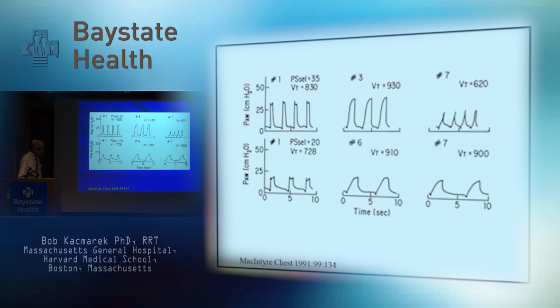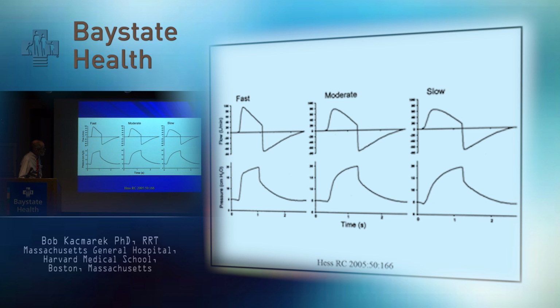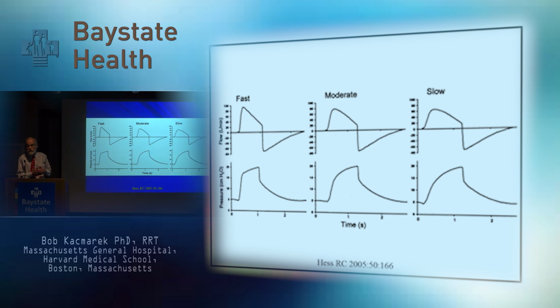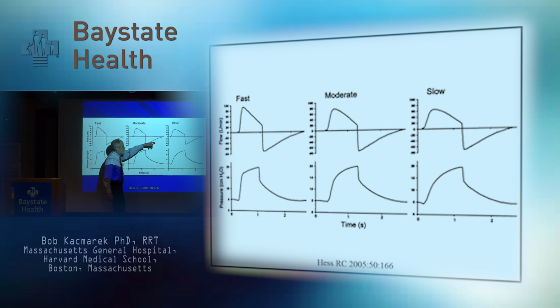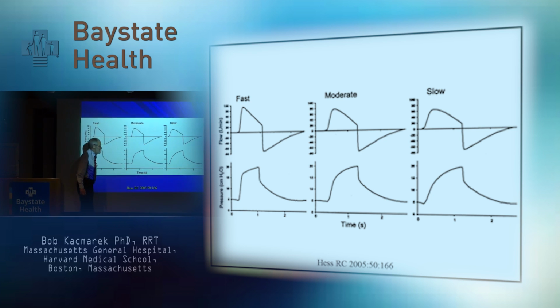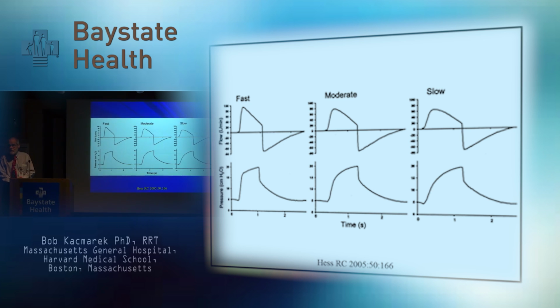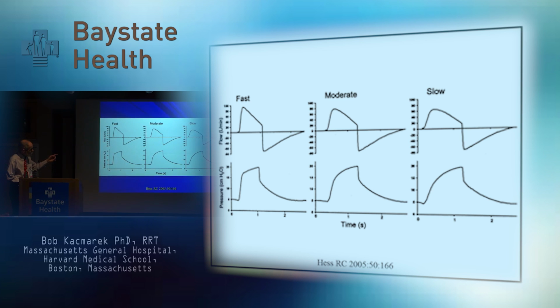And in every mechanical ventilator that I'm aware of today that delivers pressure modes of ventilation, in all pressure-targeted modes of ventilation, rise time is operational. So it allows you to vary how quickly flow goes from 0 to maximum. And in doing that, there is some change in the peak flow that's actually developed. And what we should be doing is making that adjustment in order to ensure that the delivery of pressure-targeted ventilation, again, doesn't result in flow asynchrony.